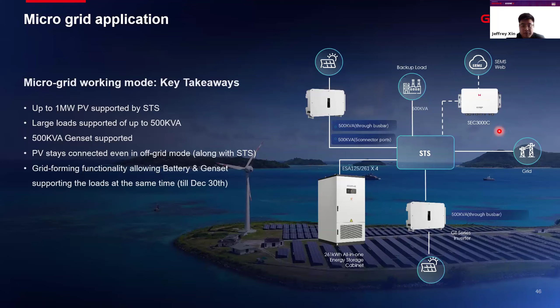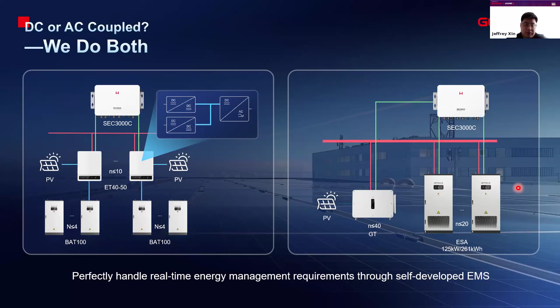For AC coupling versus DC coupling — choosing between the hybrid inverter or the PCS depends on the project. For new installations, where you're just connecting panels with the inverter, DC coupling with the hybrid inverter is better. But if a project already has an on-grid inverter installed, and you're adding a battery, AC coupling is the proper solution — that's the PCS together with the battery, which is the perfect combination.